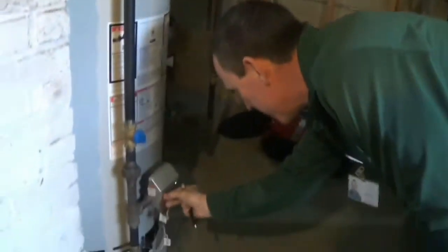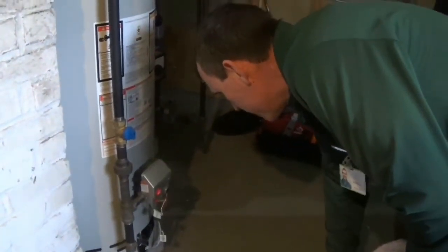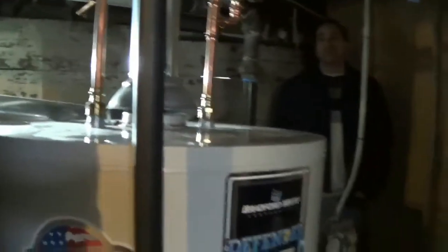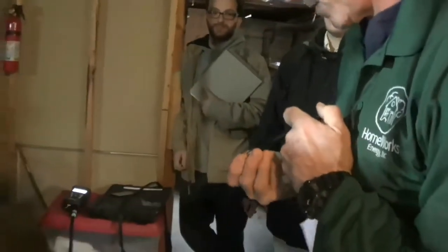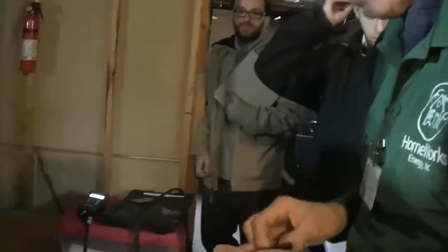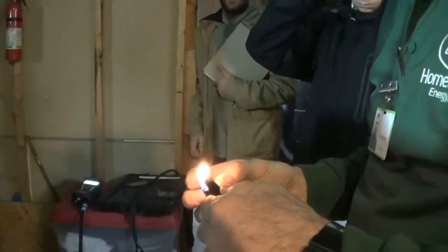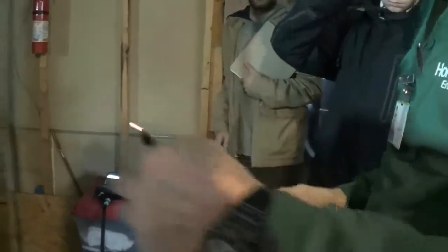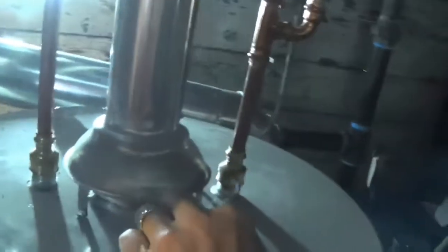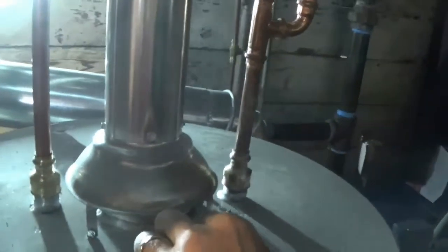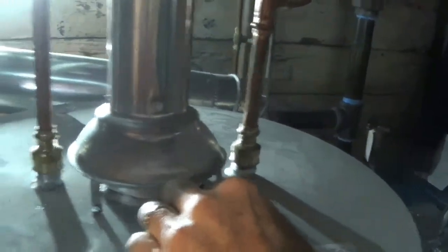About 60 seconds now. Ready? All right, listen for it. It just turned on. You can hear that roar. So 1, 2, 3, 4, 5, 6, 7, 8, 9, 10, 11, 12, 13. And I can see that smoke is not being pulled up into that flue, into that draft hood very well at all.